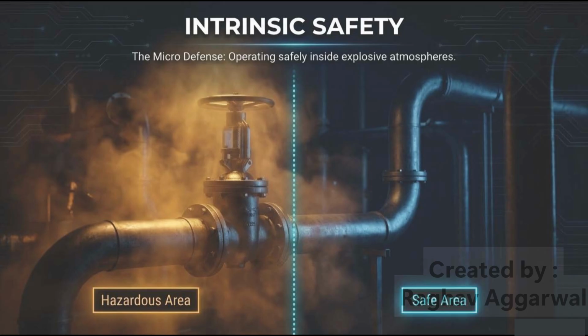The objective is to keep energy levels extremely low. This approach allows instrumentation and sensing devices to operate within hazardous environments while minimizing ignition risk. Protection is achieved through control of energy before it enters the hazardous area. Intrinsic safety is therefore a preventive strategy intended to avoid ignition rather than manage the consequences afterward.